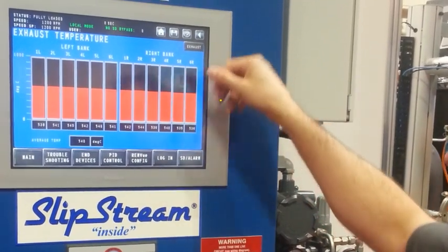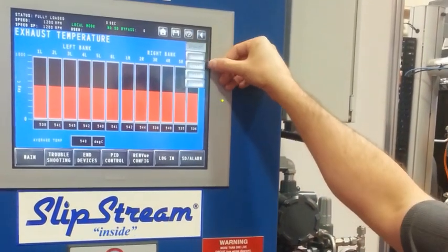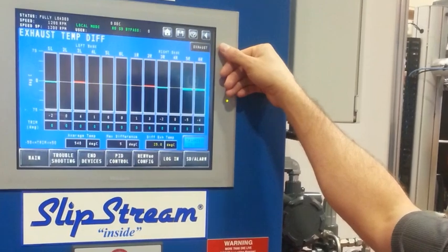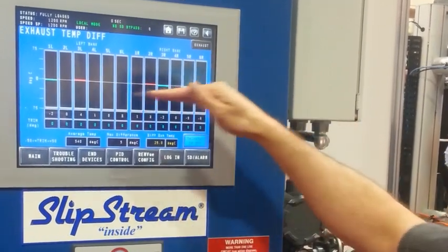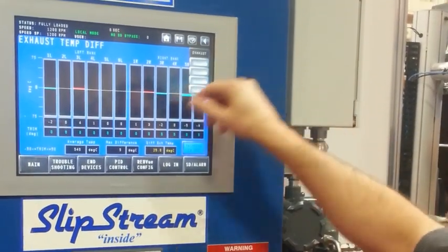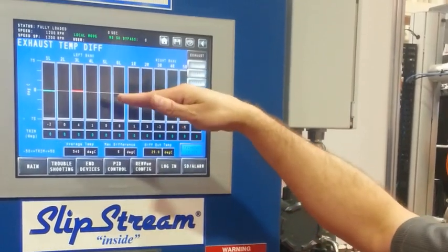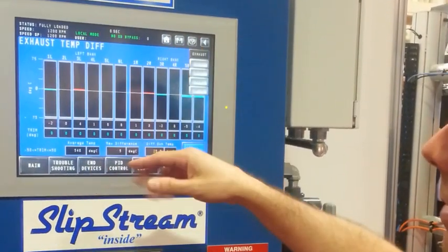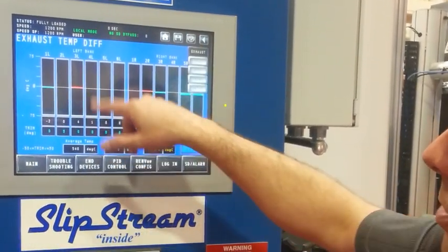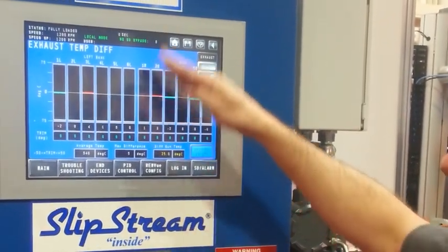Here we've got the exhaust cylinder temperature — just taking a look over them. We have differential temperatures for each of the engine cylinders. If there's a culprit where one of them is not balanced anymore, if we don't have a spark plug actually igniting the engine, it'll show us a cool spot.